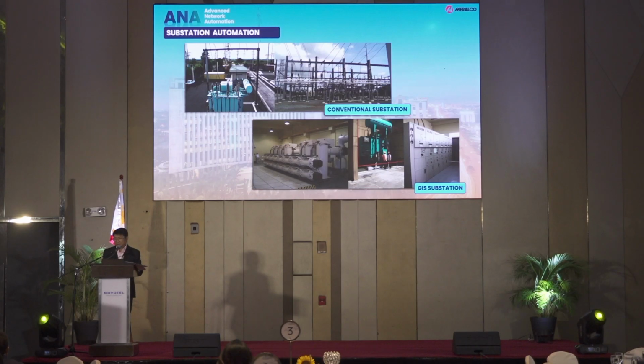Shown in the slide is our conventional substation, those A-frames, the huge switchyard, which we converted into a GIS substation. Usually we required around 3,000 square meters of lot, but now it's less than 1,000, and we're aiming for almost a very small lot of 500 square meters, and further looking into underground substations.